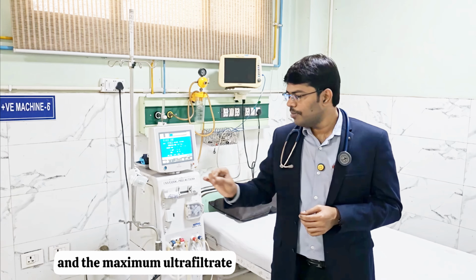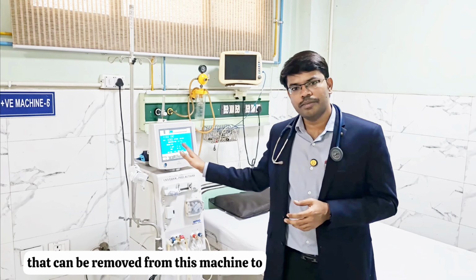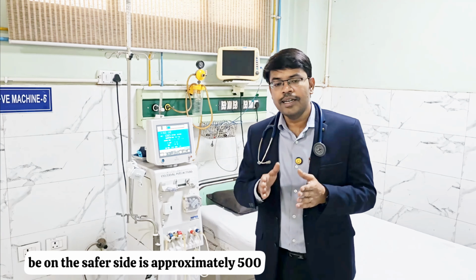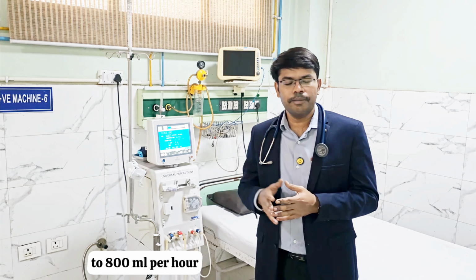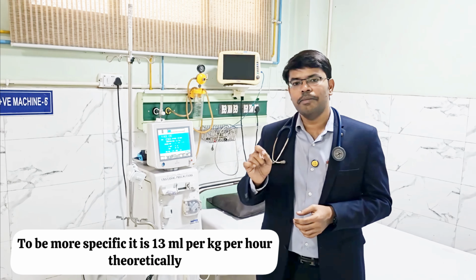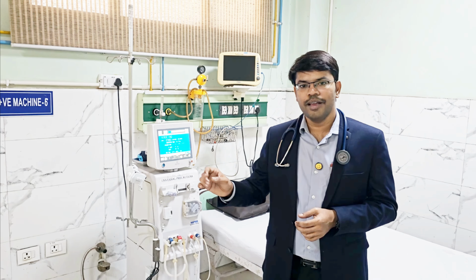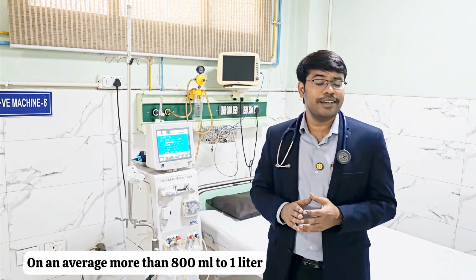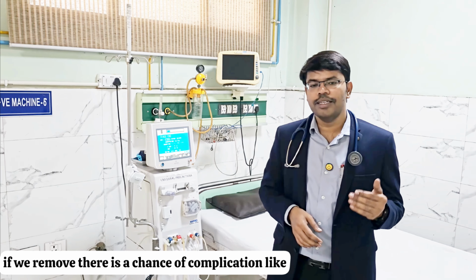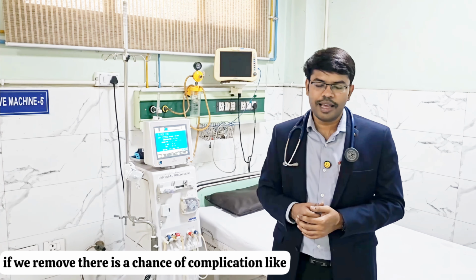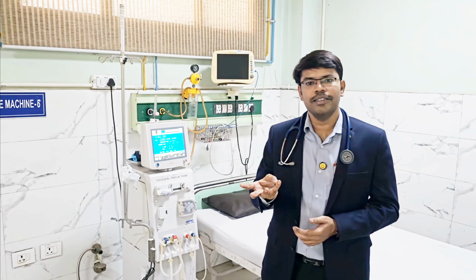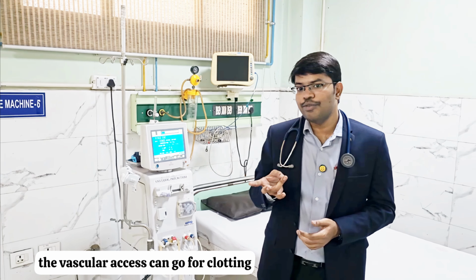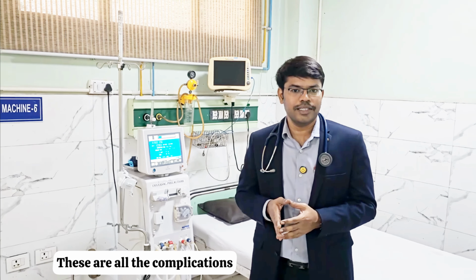And the maximum ultrafiltrate that can be removed from this machine to be on the safer side is approximately 500 to 800 ml per hour. To be more specific, it is 13 ml per kg per hour theoretically. On an average, if we remove more than 800 ml to 1 liter, there is a chance of complications like hypotension. The vascular access can go for clotting. These are all the complications.